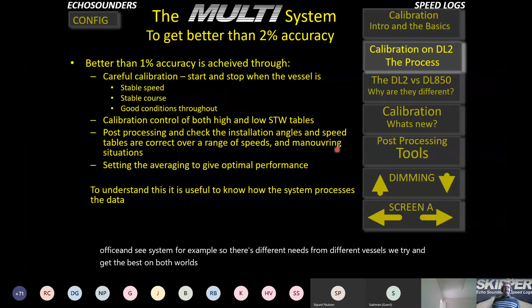To understand why we're doing the different calibrations, you need to understand the system a bit better. Now, the difference between the DL850 and the DL2: there are a few differences really. The DL2 is basically a newer generation system. The DL850 is about 20 years old, and it was using analog technology. At that time, doing replacement cards was easier than doing soldering, so the system has a lot of different cards that can be replaced.